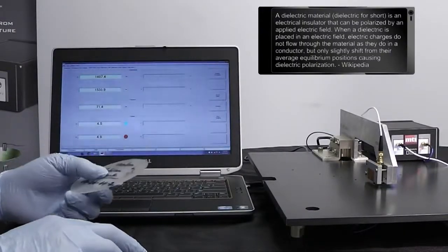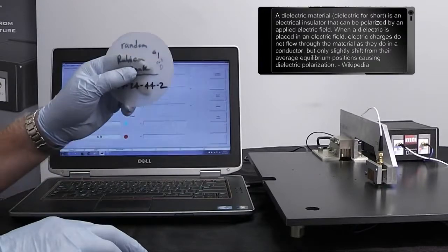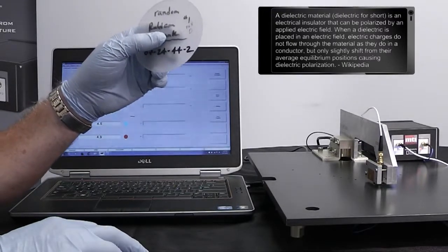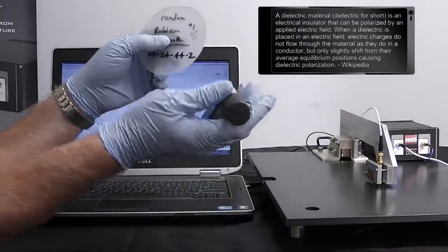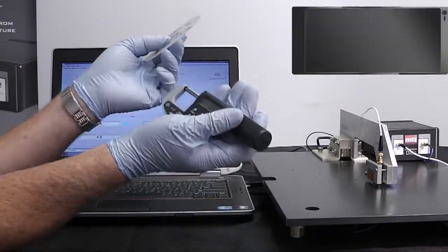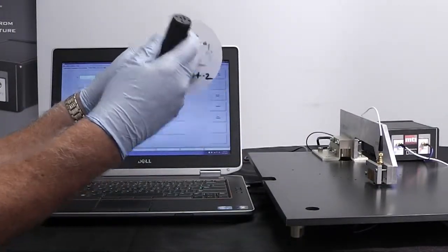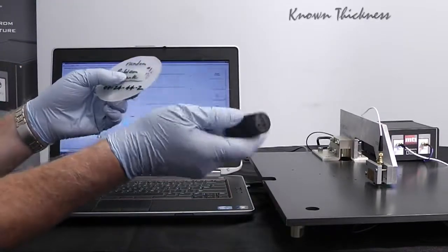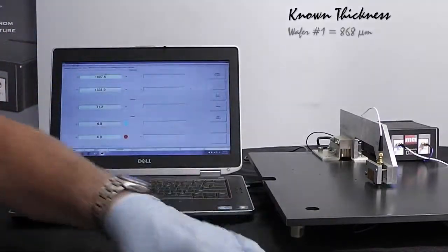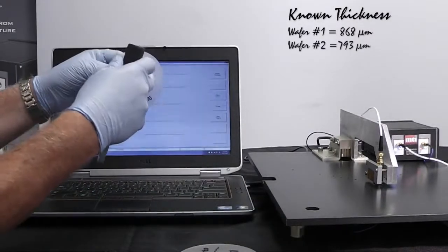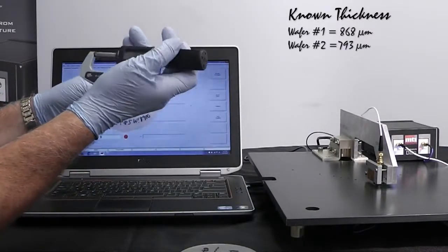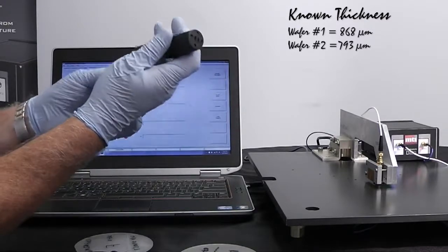After we get the program started up, what we want to do is calibrate to two known thicknesses on our sapphire wafers here. What we'll use is we have a micrometer here. I've identified two areas, one on this wafer right here where I've mic'd it and I've got 868 microns and I have a second wafer here, this one's 793 microns. We figure that out by using a standard contact micrometer to do that.